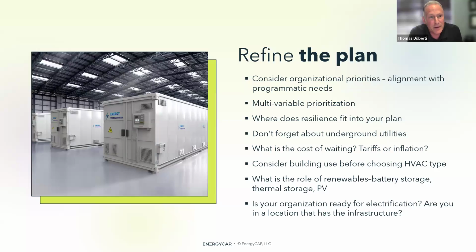Let's suppose you have a really big building and there are periods of time where there aren't a lot of people in the building and they're all in one area. And let's also suppose in this scenario that it's a building with a chiller, where when you turn the chiller on, the chiller essentially is trying to serve the whole building, and the building is designed to have a load on it. But yet, if people are only in one part of the building when the chiller is running, there might not be enough load in order to keep those people comfortable.